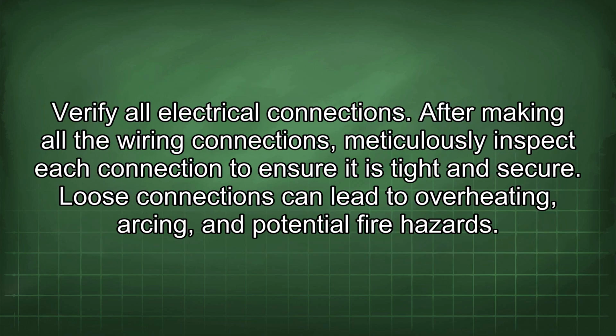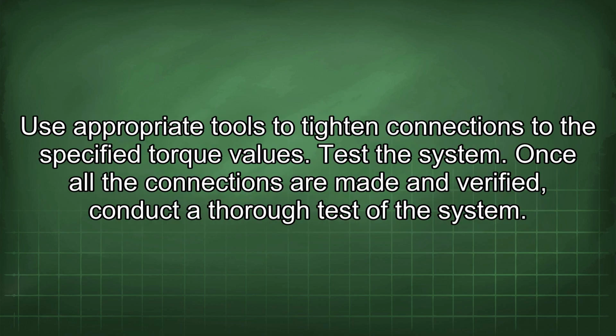Verify all electrical connections. After making all the wiring connections, meticulously inspect each connection to ensure it is tight and secure. Loose connections can lead to overheating, arcing, and potential fire hazards. Use appropriate tools to tighten connections to the specified torque values.